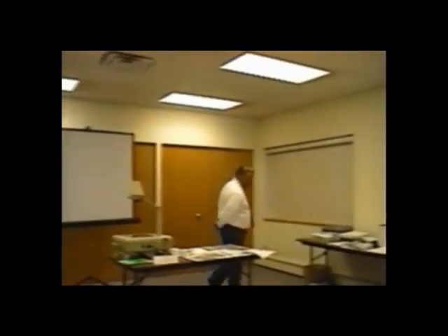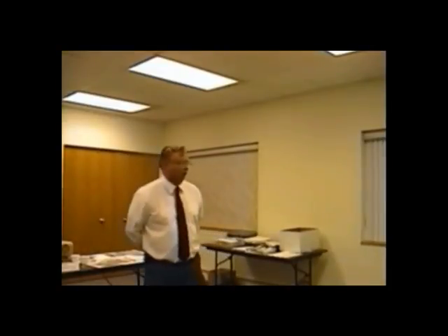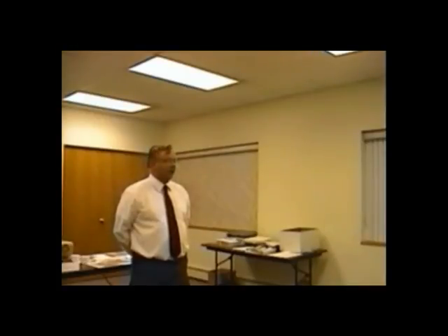Do you understand why I said right now it takes you longer to do the math than it does to recover and recharge? But once you do that math and you get quick with it, recovering and recharging is the way to go. And at that point, ladies and gentlemen, you don't have to touch that charge at all. You can leave your gauges on it to diagnose if you want. But charge is out of the question.